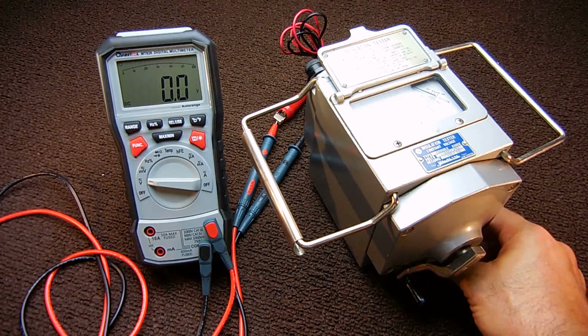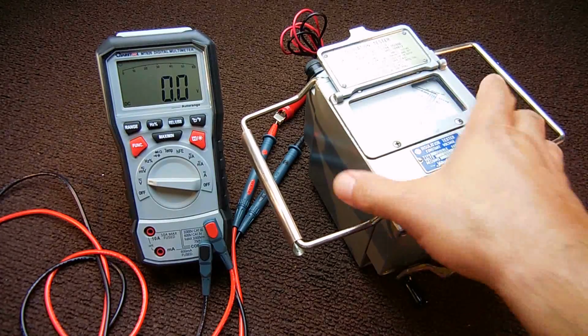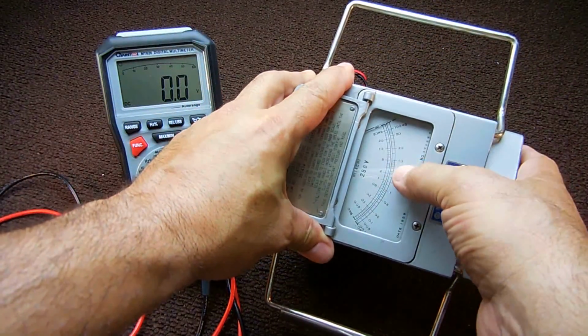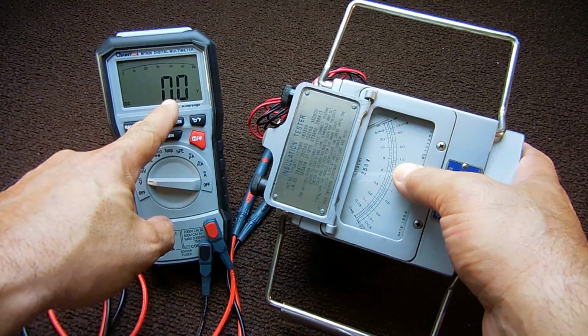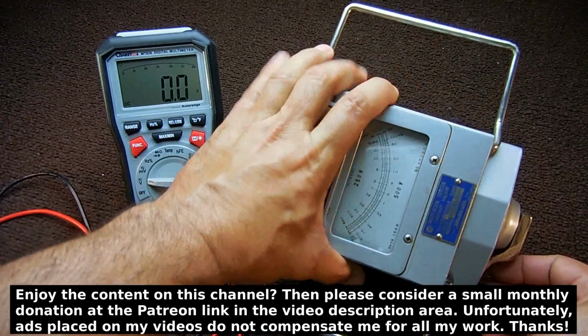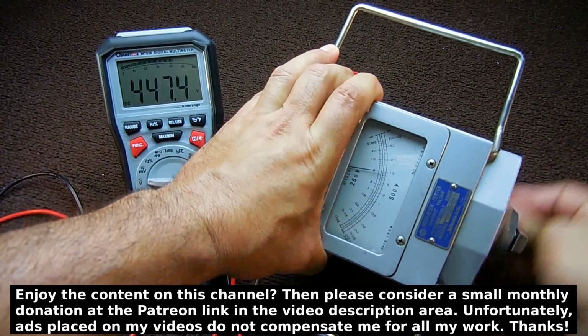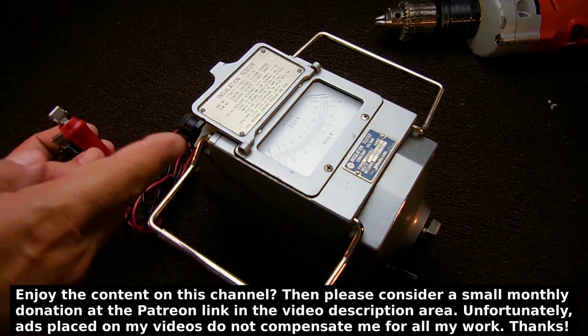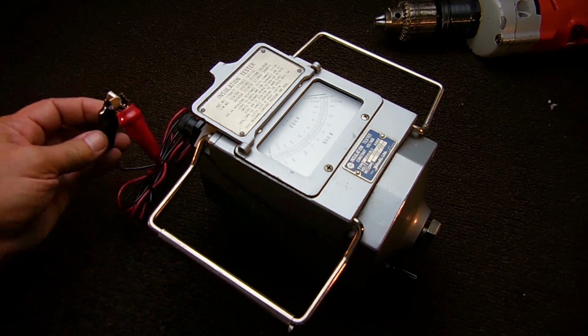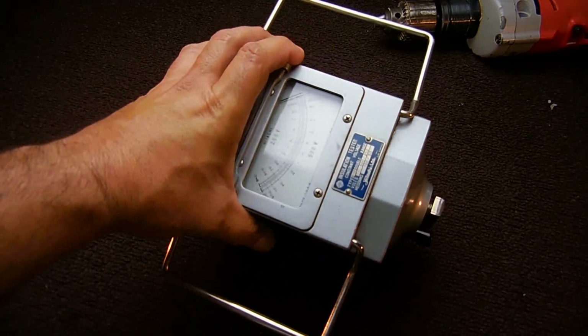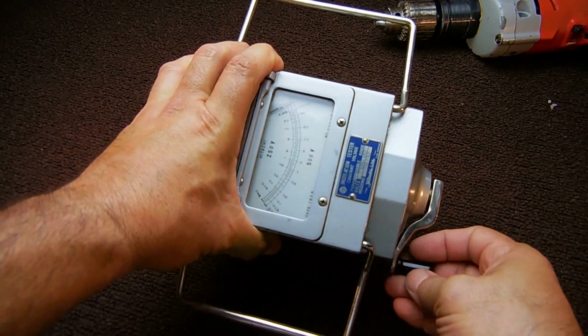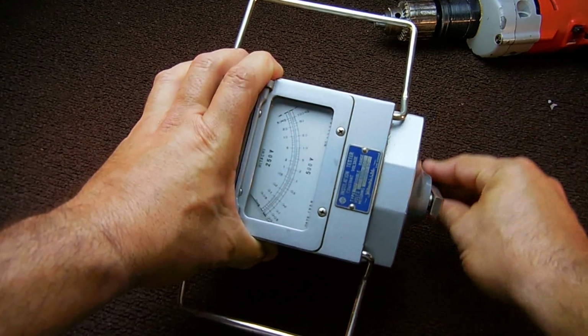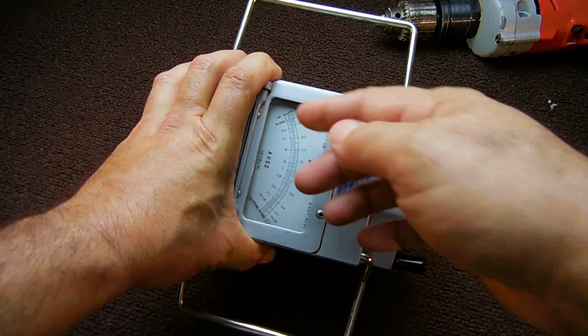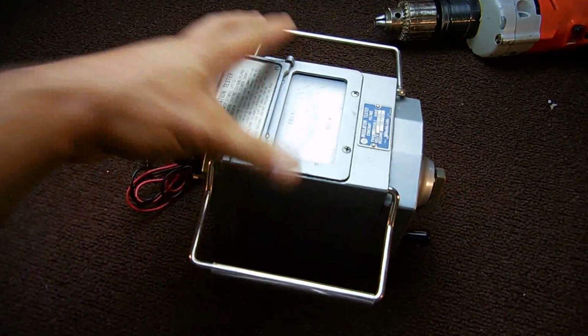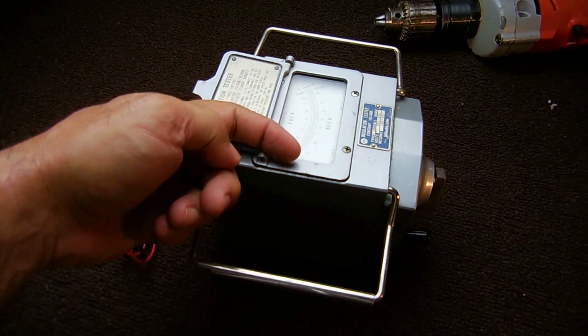Let's put it up to the 500 volt range now. We're going to be looking at the lower scale here. So the 10 should show up here, and over here we're going to see 500 to 600 volts. If you shorted these two wires together, you would see that the needle would swing all the way to the right when you go to crank. So let me short those together, tilt it so you can see the meter, and crank it. And there you go, all the way down towards 0 ohms. I just wanted to show you that because you might say everything's coming out the same at the top. But as you can see, if the resistance is very low, this will swing all the way down.